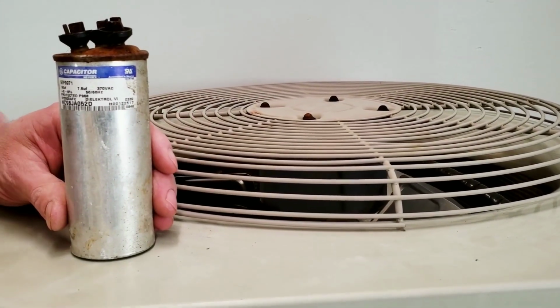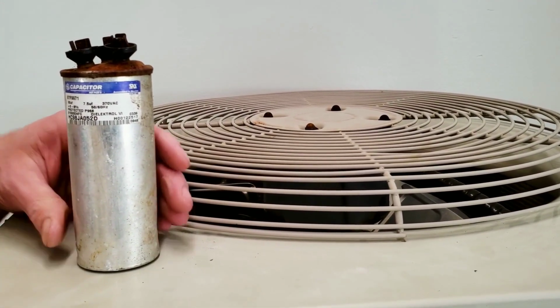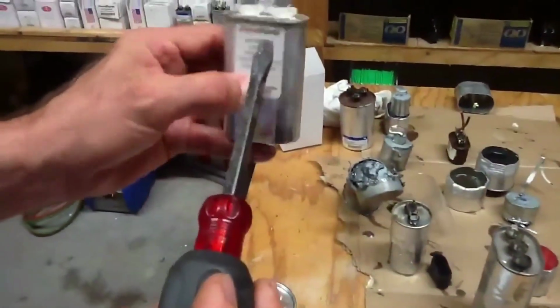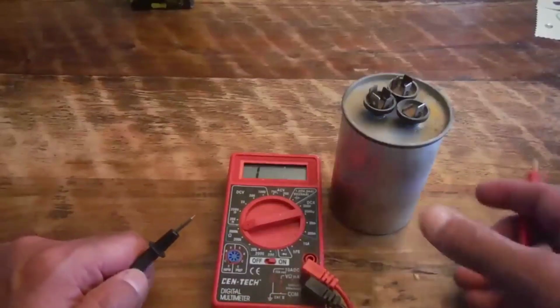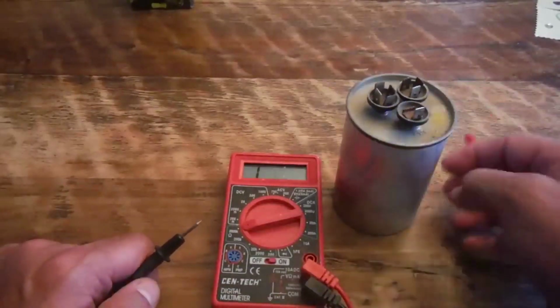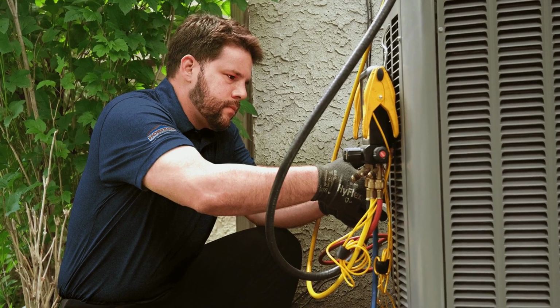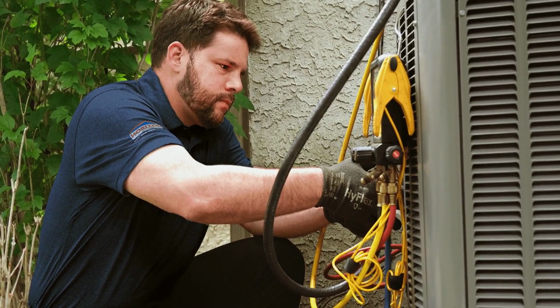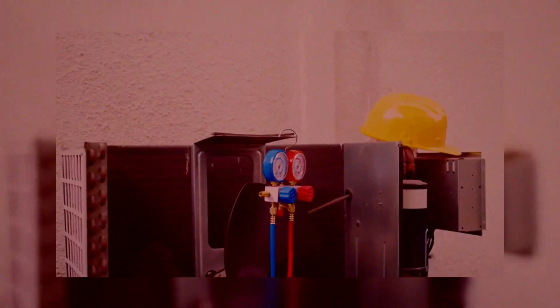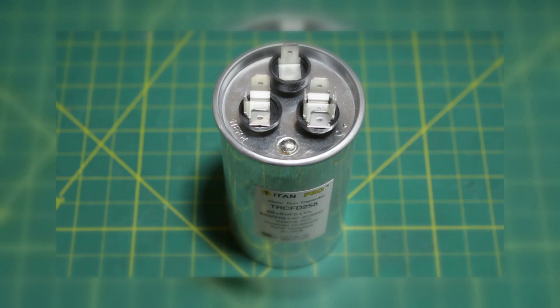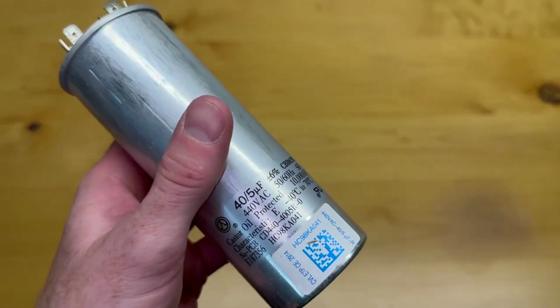The first number is the microfarad rating, abbreviated micro F. This is the capacitance value, and it must match exactly. Common dual-run capacitor ratings pair values like 45/5 microfarad or 35/5 microfarad, representing the compressor side and the fan side respectively. Running a capacitor with the wrong microfarad rating causes motor strain, overheating, and premature failure of the compressor or fan motor, components that cost hundreds to thousands of dollars to replace. Do not approximate this number. Match it precisely.